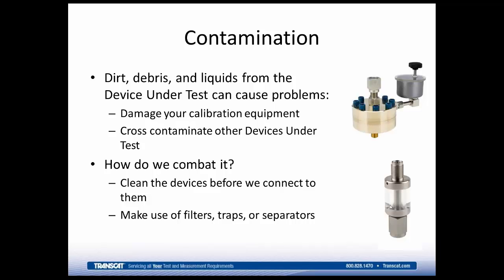A separator or a trap is like this device below that has the clear acrylic walls. Say your device under test is connected to the top, and your reference is connected below. For the pressure to go, or the debris to go, from the device under test to the main unit, it's got to go up or go down, back up, and back down again, and that acts as a gravity trap that will keep the debris from reaching the standard.